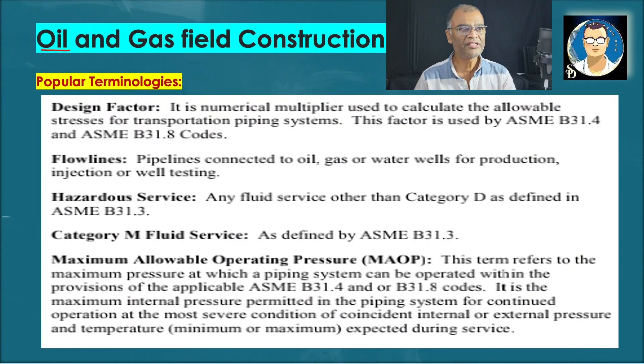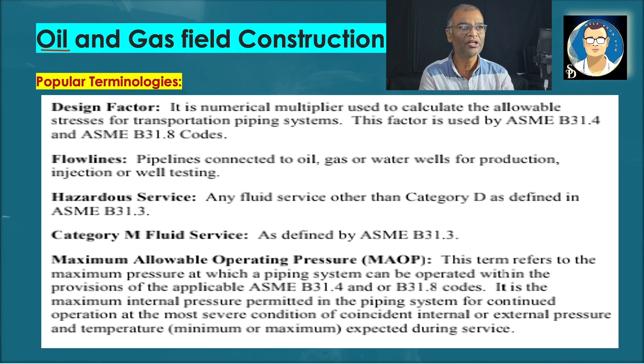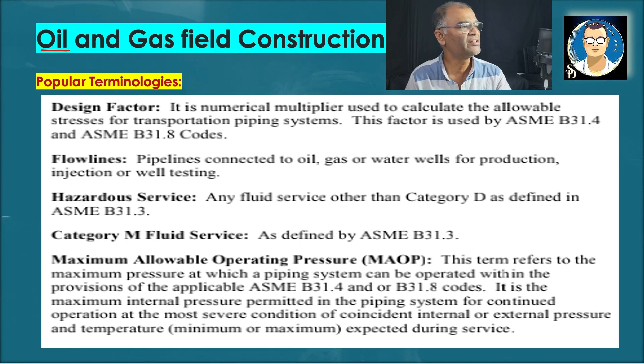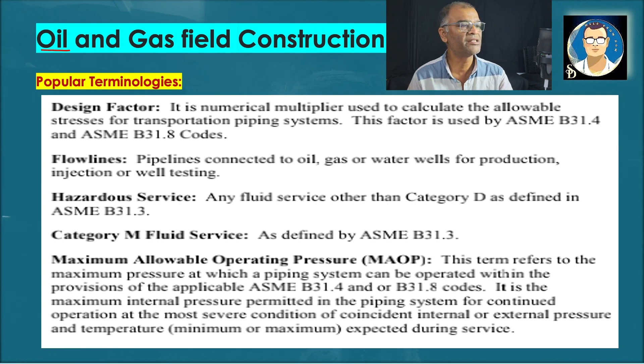Design factor: it is a numerical multiplier used to calculate the allowable stresses for transportation piping systems. This factor is used by ASME B31.4 and B31.8. Flow lines are pipelines connected to oil, gas, or water wells for production, injection, or well testing. Hazardous service refers to any fluid service other than Category D as defined in B31.3. Category M fluid service is as defined by ASME B31.3.